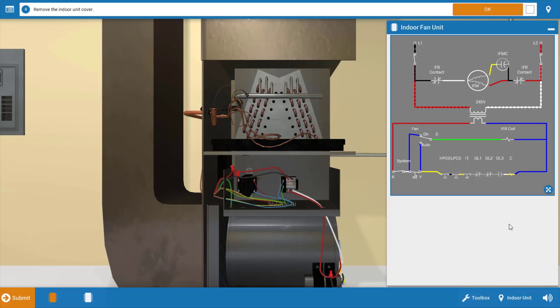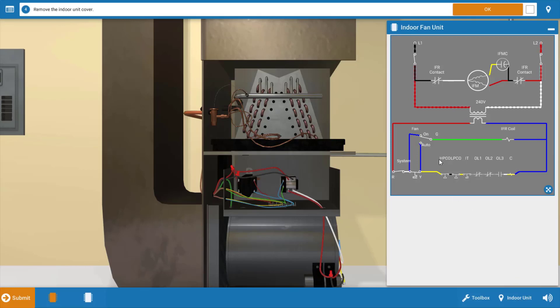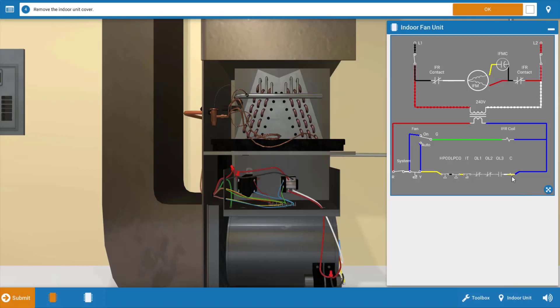Now we know that none of the motors are operating, and if we take a look that could mean that we don't have power coming into the indoor unit, which would basically not allow the transformer to provide 24 volts to the relays here. It's also possible we have a bad transformer or possibly a faulty thermostat. Now if you look, all three of these provide power to both the indoor fan relay coil, which turns on the indoor fan, as well as the contactor coil in the outdoor unit, which when energized will turn on both the outdoor fan or condenser fan as well as the compressor.